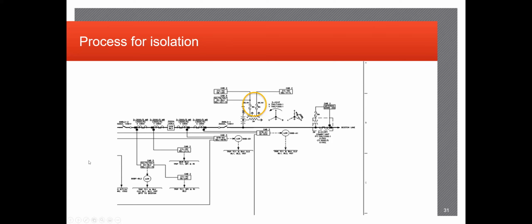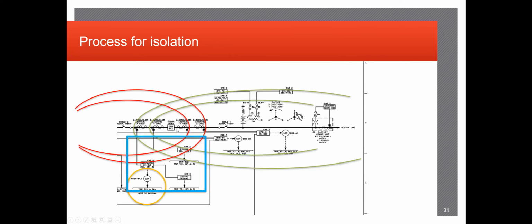So in our case specifically, the order of operations for the high side of this string would probably be to open up this breaker, and open up each of these motor operated switches to completely and utterly isolate this entire string of CTs and the breaker itself. Because if you were to just open this breaker up, there could still be some sort of floating current coming into these CTs when working in the cabinets as well. So it just leads to more risks, and it's better to isolate the entire section itself with these switches.